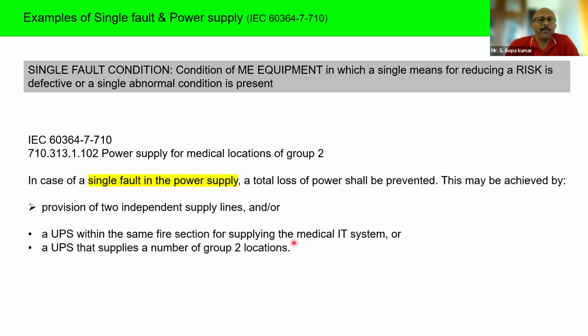The purpose of showing this particular slide is that this part of the standard explains a UPS supplying the medical IT system. Unfortunately, in several places, UPS are being used as a medical IT system, which is wrong. UPS is a different item. UPS ensures that in case of a single fault, the power supply continuity is ensured, whereas medical IT system is a different subject.